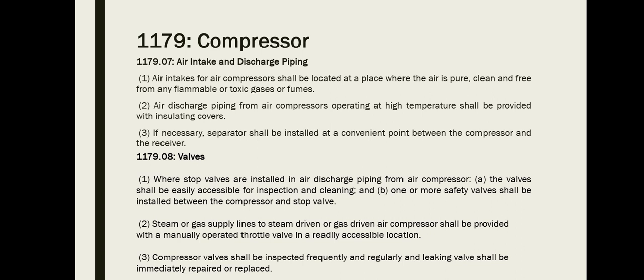So, Rule 1179.08 is Valves. First, where stop valves are installed in air discharge piping from air compressors, A, the valve shall be easily accessible for inspection and cleaning. So kung install nimo sa air discharge piping sa air compressor, dali ra ma-access ang pag-inspect ug pag-limpyo. Then B, one or more safety valves shall be installed between the compressor and stop valve. So isa or daghan nga safety valves dapat install sa tunga sa compressor ug stop valves.